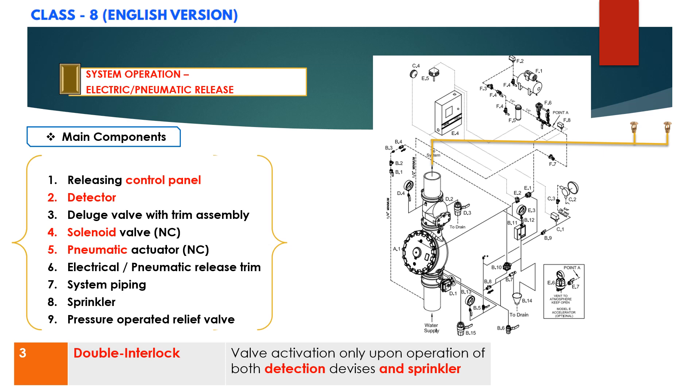When the deluge valve A1 operates, then the sensing end of the PORV B10 is pressurized causing the PORV to operate, and the water will flow through the PORV to the drain.